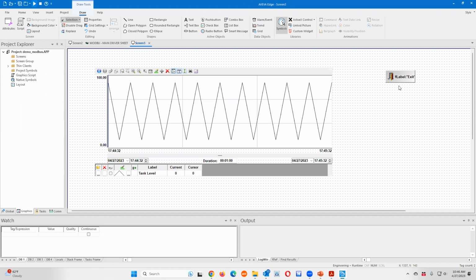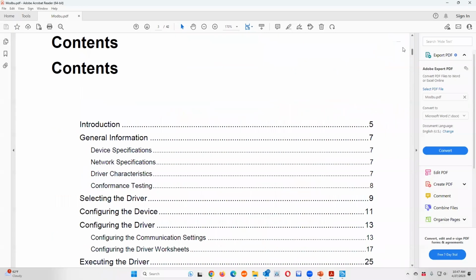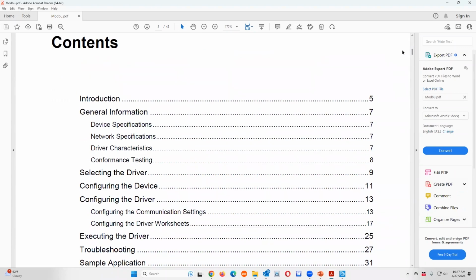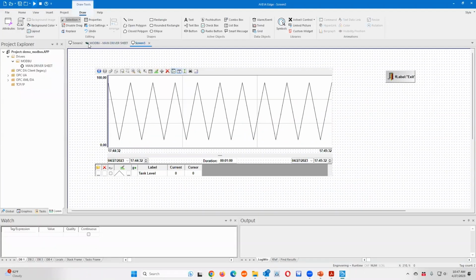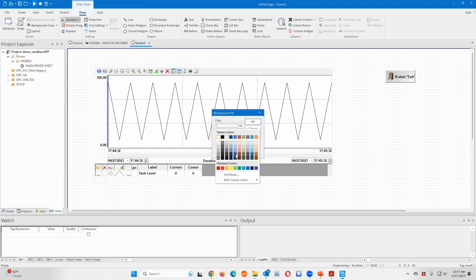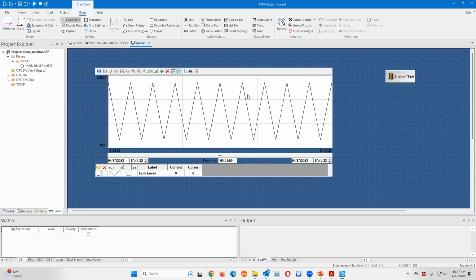Does anyone have any questions on creating connection? Again, the most important thing is making sure that the correct driver is chosen for the project. And again, use the help documents, like for instance, the Modbus one, to determine how to configure the connection and how to create the tags associated with those objects. Then from there, you want to use your animations or drawing widgets to visually show your project. If you want to create a background image, that's also another thing you want to do. You can simply do background color, or you can add a background image by right-clicking. And in this case, you can do background color. I want to change it to like this color. Just change everything, or you can create a picture and just put it in the background as well. And be sure to bring these other objects to the front.